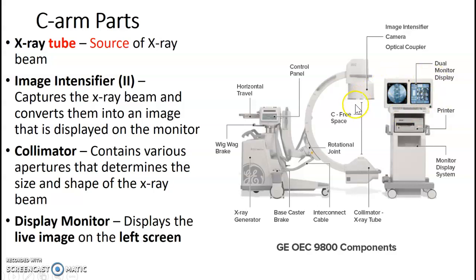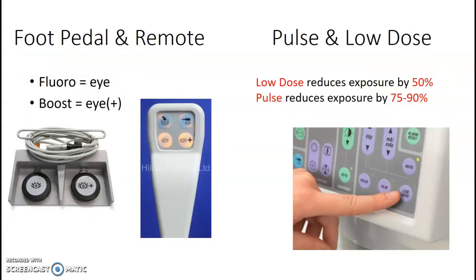The collimator is within it, and it contains various apertures, and determines the size and shape of your X-ray beam, and I'll go into that in a little more detail later on. And then the display monitor, the live screen when you're fluoroing, is on the left side, and if you save and swap, it'll go over to the right. We have both the 9800 GE OECs and the 9900s at our clinical site.